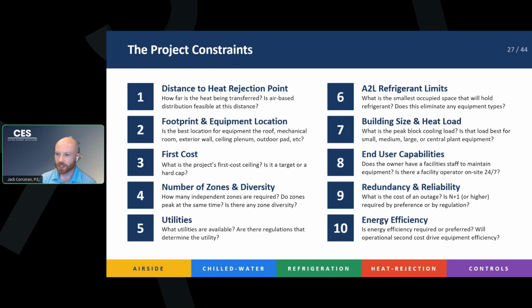Our distance to heat rejection point, how far away is our occupied space from the roof, right? We know packaged rooftop units need to go on the roof. If we have a 50-story building in Manhattan, we're not going to be running our ductwork all the way down to the first floor. Maybe that eliminates it, and you want to use chilled water instead. Same thing with number 2, our footprint and our equipment location. I just said it, the roof is a very, very dominant constraint for rooftop units. That's where the unit is located. So even if you have a bunch of mechanical rooms in your building, you still have to have this thing on the roof. Maybe if you have mechanical rooms throughout your space, you're going to maybe look at a different solution instead of running with rooftop units.